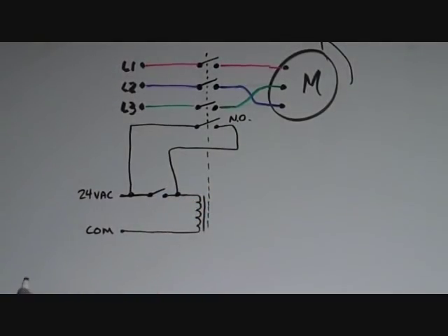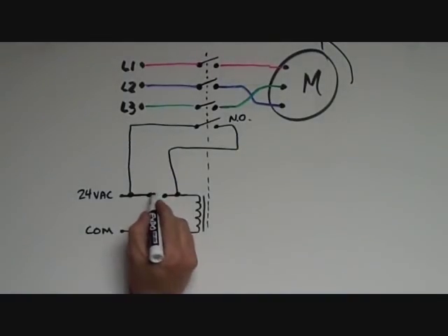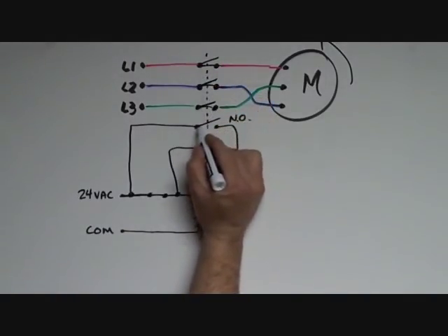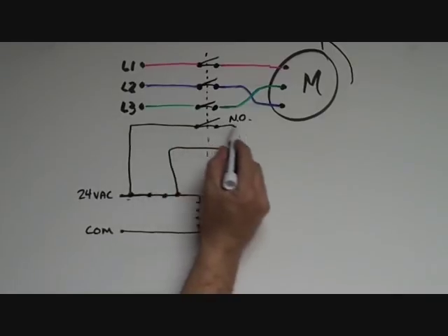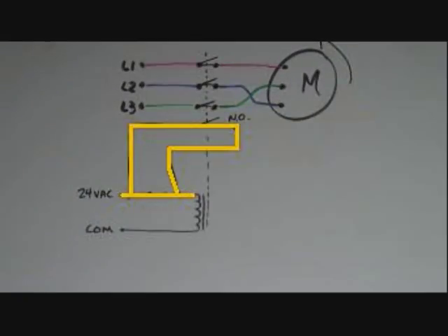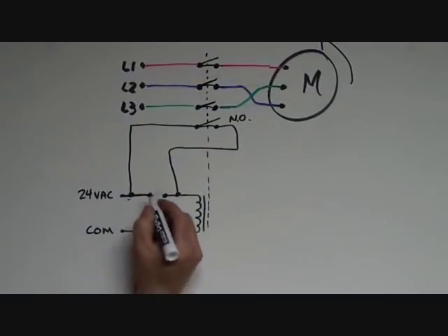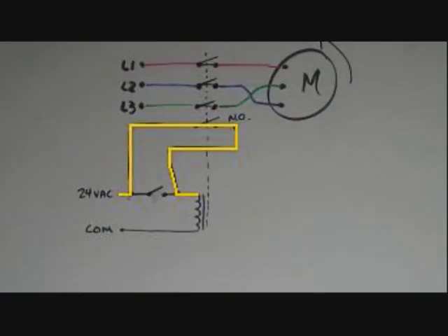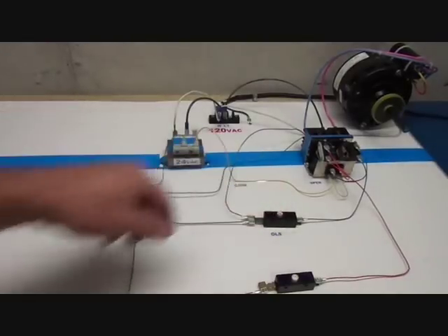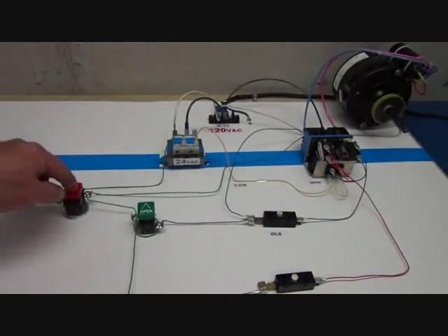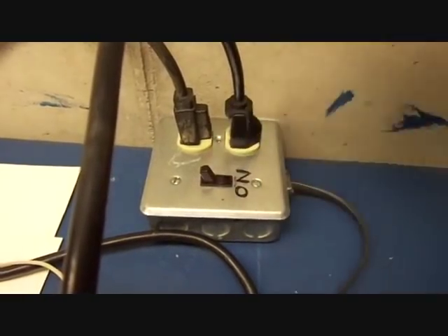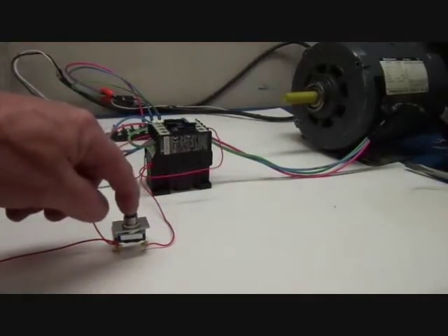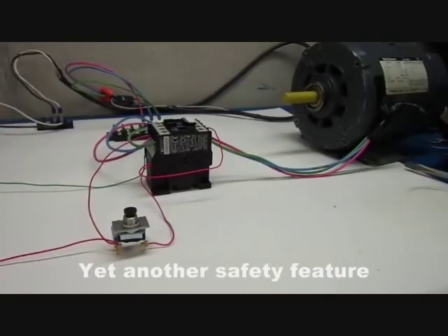So right now there's no power going to the coil. When I press the push button, it sends 24 volts to the coil like normal, pulls in the contacts and the motor runs. When the contacts close, that normally open contact, that fourth pole, also closes. So A1 is getting its 24 volts through two different paths. When I let go of the push button, A1 is still getting 24 volts from the fourth set of contacts, so the coil is still getting power and the motor stays running, until that 24 volts is interrupted by something like a limit switch or a stop button, which would be a normally closed switch somewhere in series before the push button. And if the power went out while this motor was running, it wouldn't start back up when the power was restored. You would have to restart it by pressing the push button. This way you don't have a bunch of machines all fire up at the same time when the power comes back on.